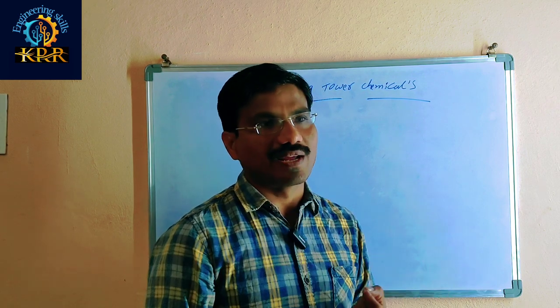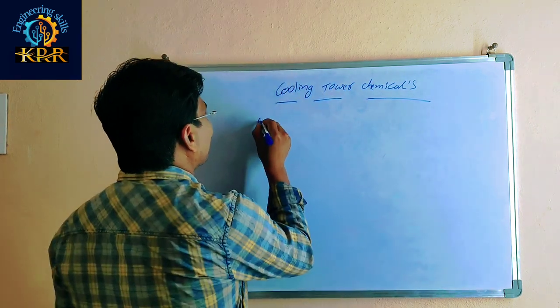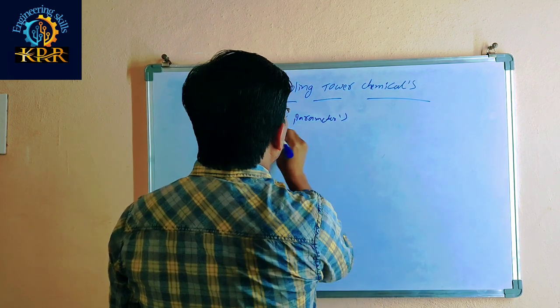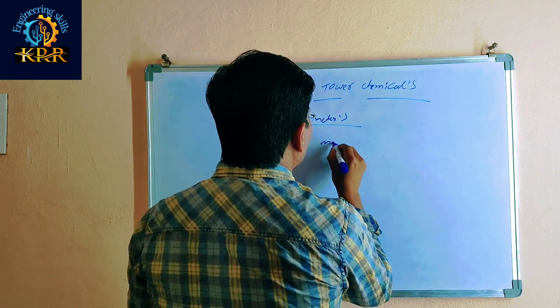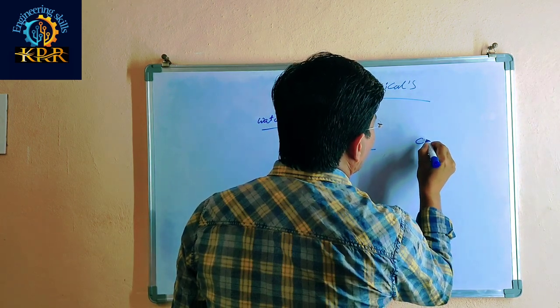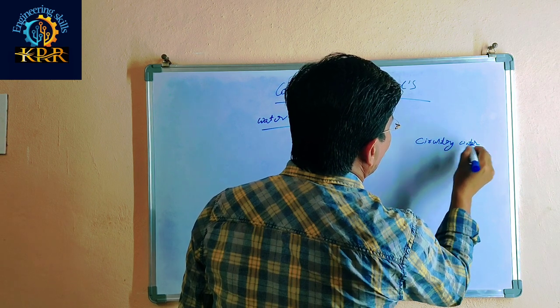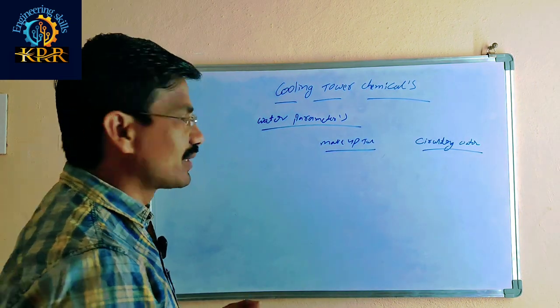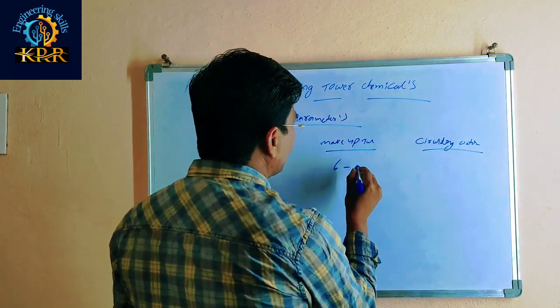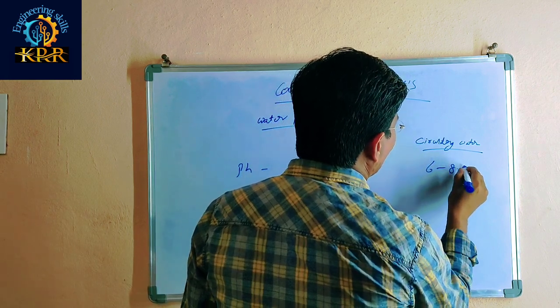Using these chemicals, we can control the water parameters. The parameters apply to both the makeup tank water and the circulation water. For pH value: in makeup water it should be maintained at 6 to 8, and in circulating water 6 to 8.5.